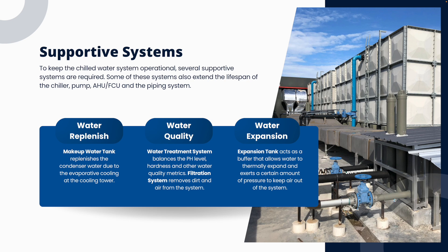Now let's talk about the supportive systems — the systems that keep the chilled water system operational and extend the lifespan of various components. The first is water replenishment. When the cooling tower cools down the condenser water, some of that water evaporates, causing the water level to drop. That's why we need a make-up water tank to hold water and automatically refill the cooling tower basin. When the basin level drops to a certain point, this water flows in to top it up.